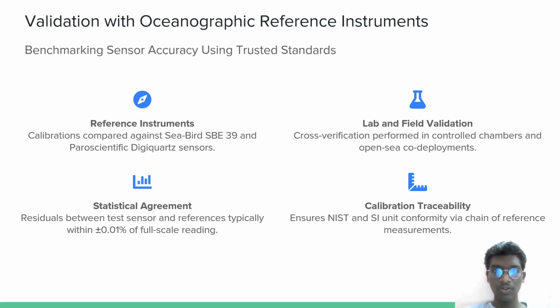Validation with oceanographic reference instruments: benchmarking sensor accuracy using trusted standard reference instrumentation. Calibration was compared against the Sea-Bird SBE 39 and Paroscientific Digiquartz sensors. Lab and field validation: cross verification performed in a controlled chamber and open sea co-deployment. Strong agreement is reached between the test sensor and reference, typically within plus or minus 0.01 percent of full-scale readings. Calibration traceability ensures NIST and SI units conformity via chain of reference and measurements.